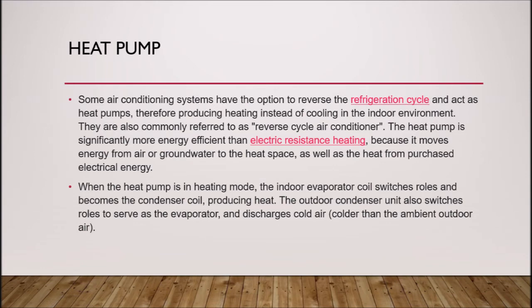Heat pump. Some air conditioning systems have the option to reverse the refrigeration cycle and act as a heat pump, therefore producing heat instead of cooling in the indoor environment. They are also commonly referred to as reverse cycle air conditioners. The heat pump is significantly more energy efficient than electric resistance heating because it moves energy from the air or groundwater to the heated space, as well as the heat from purchased electrical energy. When the heat pump is in heating mode, the indoor evaporator coil switches role and becomes the condenser coil, producing heat. The outdoor condenser unit also switches role to serve as the evaporator and discharges cool air, cooler than the ambient outdoor air.